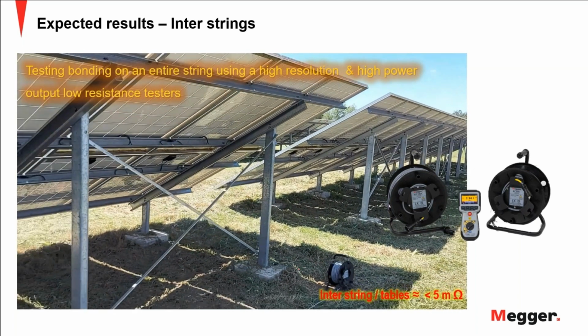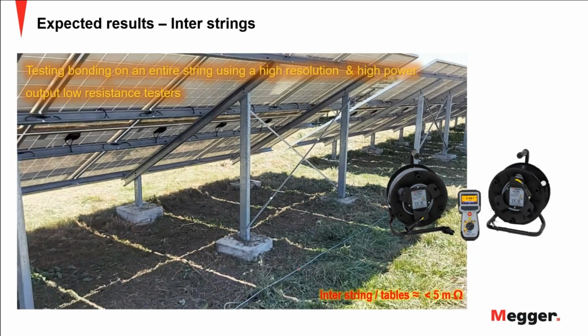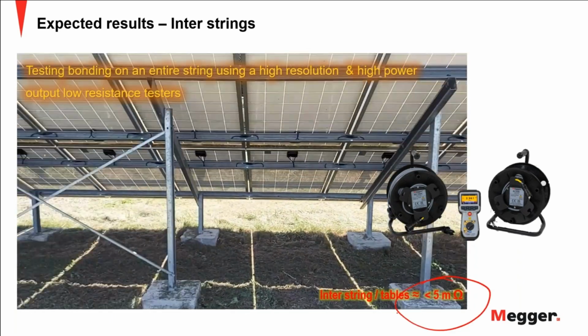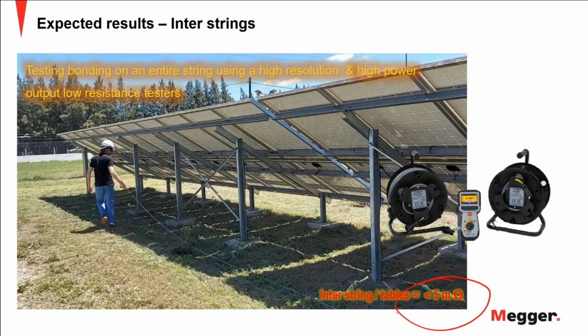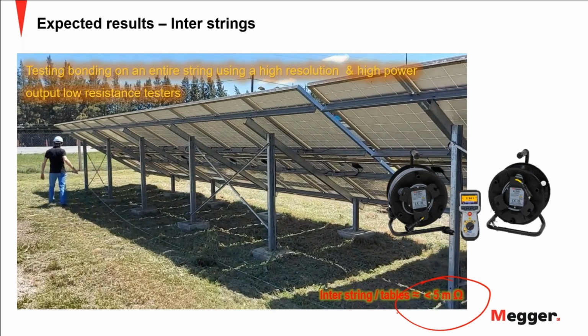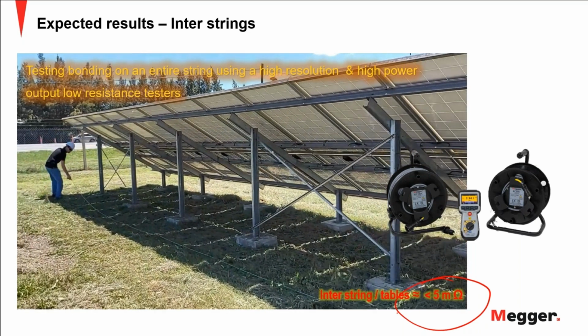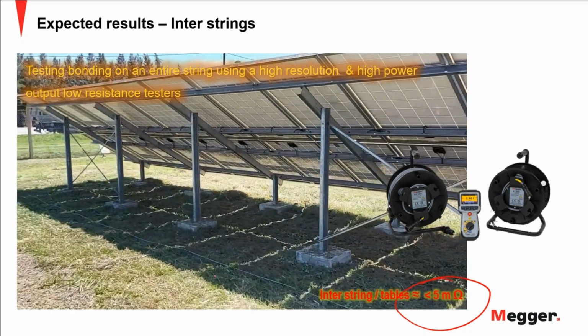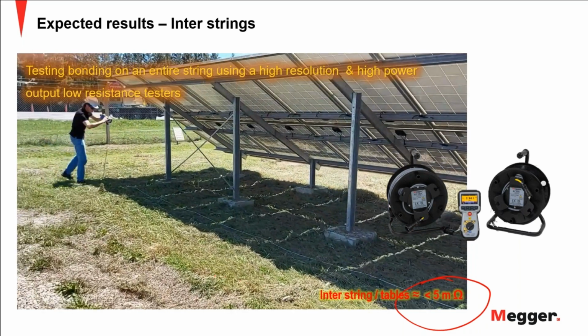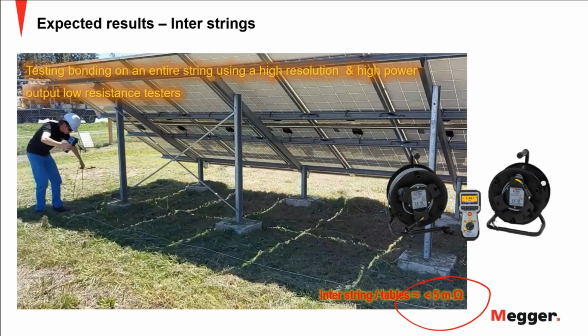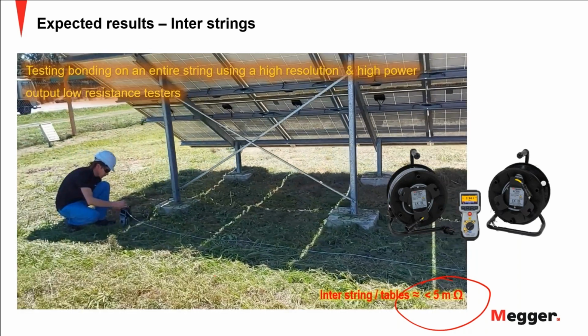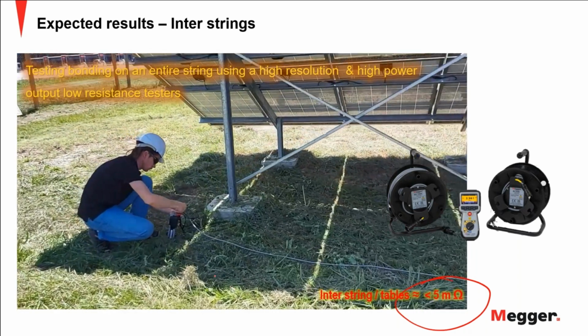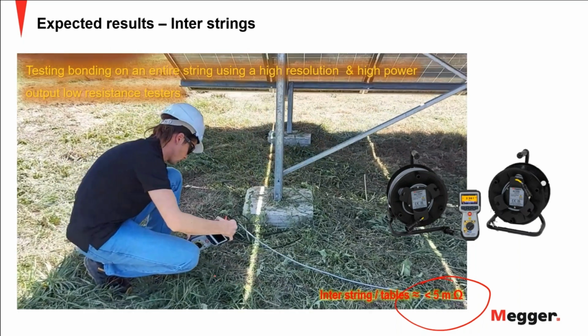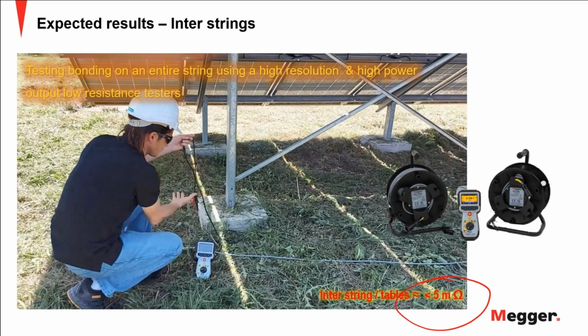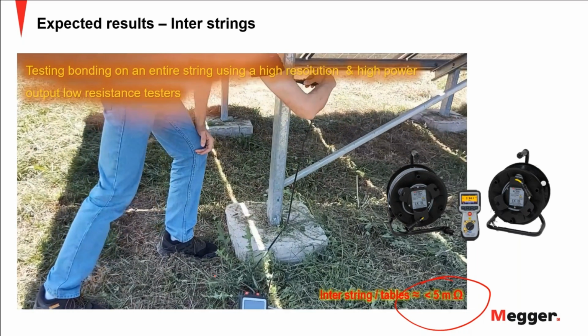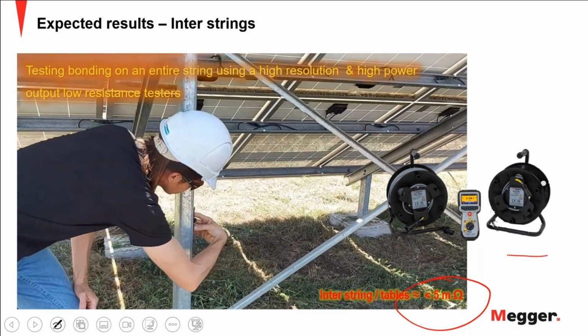The typical measurement that you expect is 5 milliohms or below for all of these bonding connections. In this case, the ideal thing is to use a high resolution instrument with high power. Now you have a long path to measure, and you want an instrument that can give you the resolution and the current to perform this measurement.